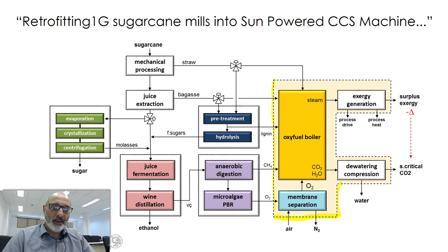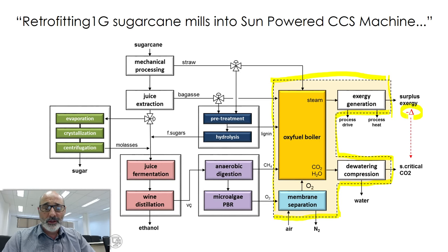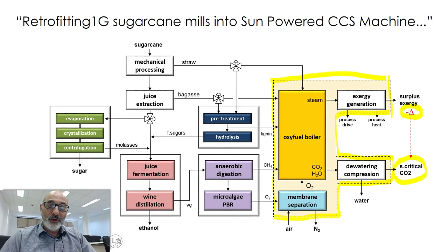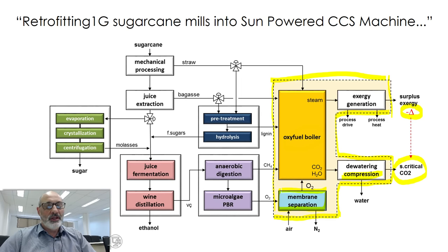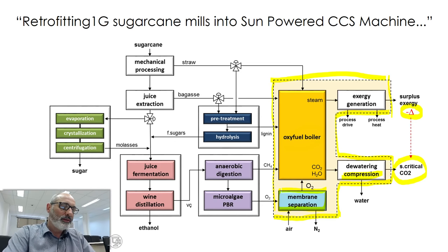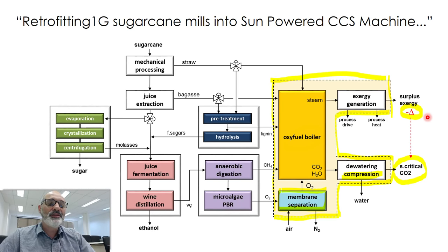We've already made the modifications to transform this to a supercritical CO2 producer. The idea is to take some amount of energy and invest it to produce supercritical CO2. This energy delta is used for the most part in oxygen separation for the oxy-fuel boiler and also to compress CO2 to the pressures corresponding to supercritical CO2. The whole point for the process to be technically feasible is that the remaining surplus is still positive.